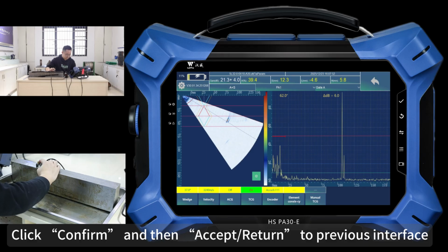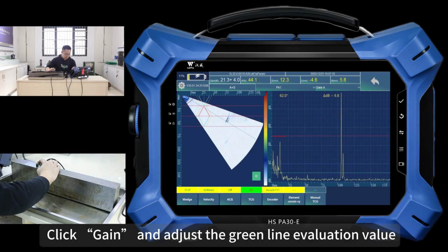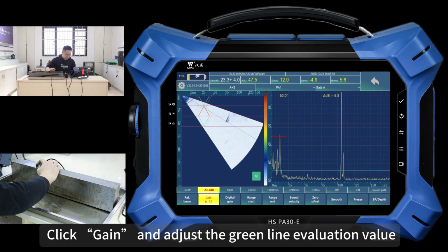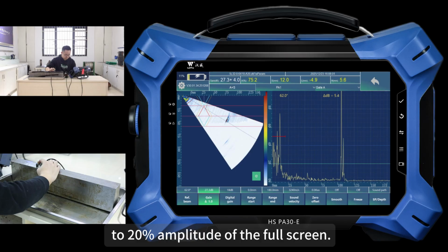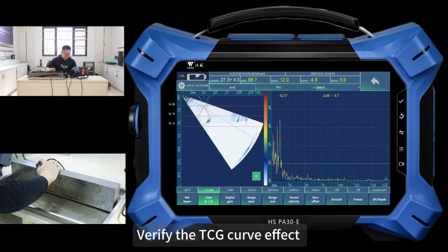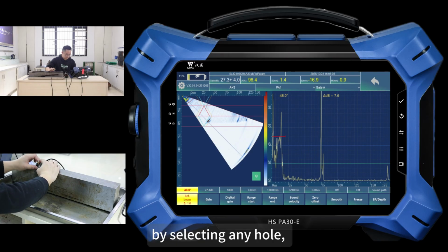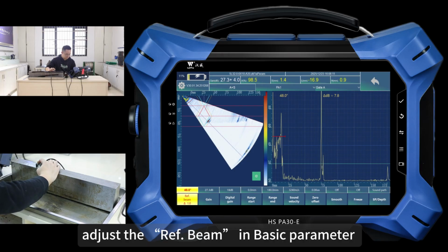Return to previous interface. Click Gain and adjust the green line evaluation value to 20% amplitude of the full screen. Verify the TCG curve effect by selecting any hole. Adjust the Ref. Beam in basic parameter, and gate start.